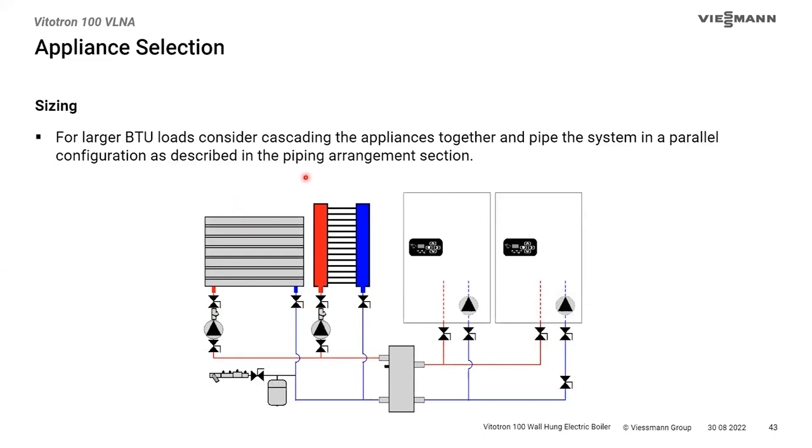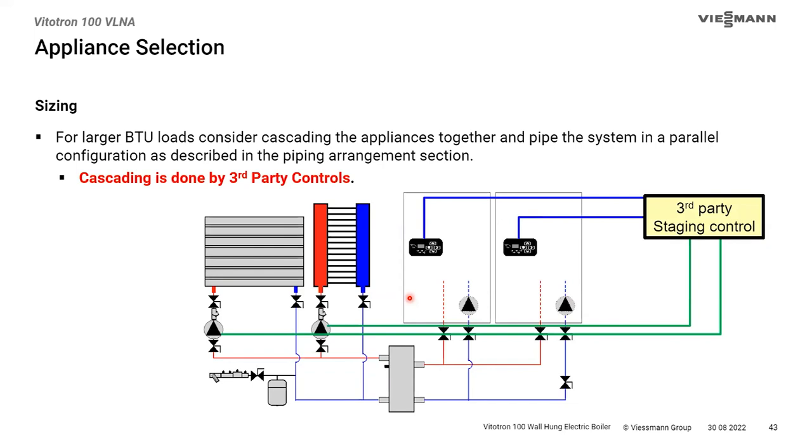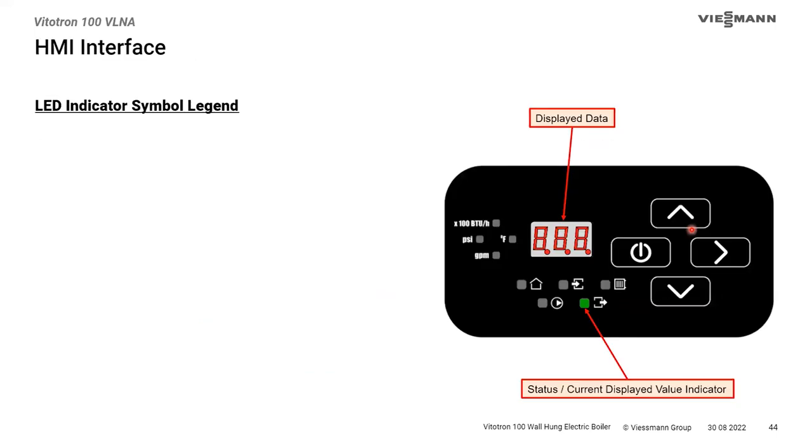For larger systems, you might want primary/secondary piping and more than one boiler. You can stage these boilers as much as you want. The challenge is that Viessmann doesn't currently have a control for this, so you'd need a third-party staging control that can also manage your downstream pumps. The auxiliary pump output on the boiler won't be able to handle multi-boiler staging, so a third-party control is required.